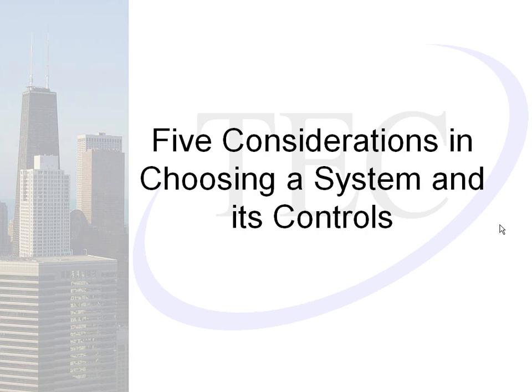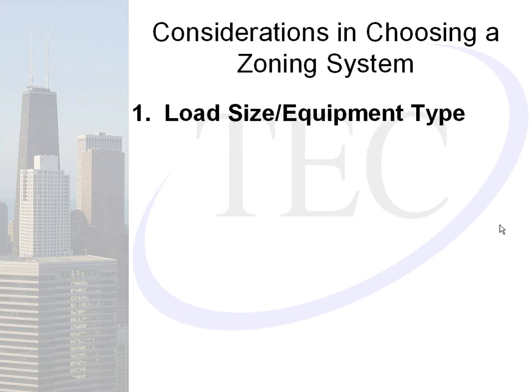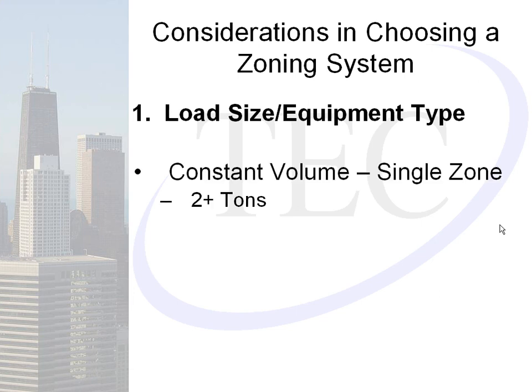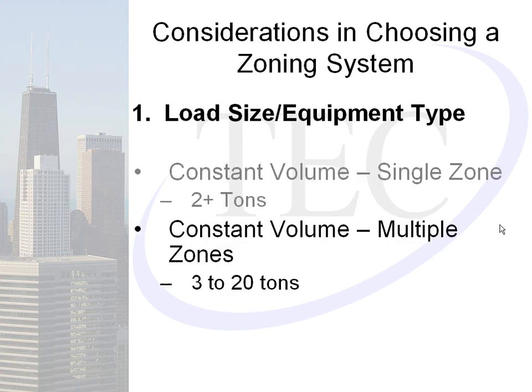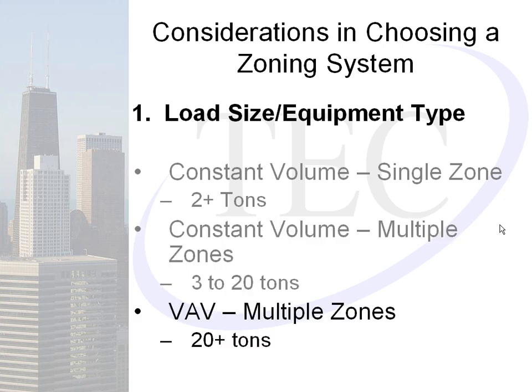When considering which of the three systems you want to install or design, there are five considerations. The first is load size or equipment type. Constant volume would typically be used in any application that only requires a single zone of temperature control, from two tons on up. Constant volume multiple zones is typically used between three and twenty tons. VAV multiple zones would typically be used anywhere from twenty tons and up.